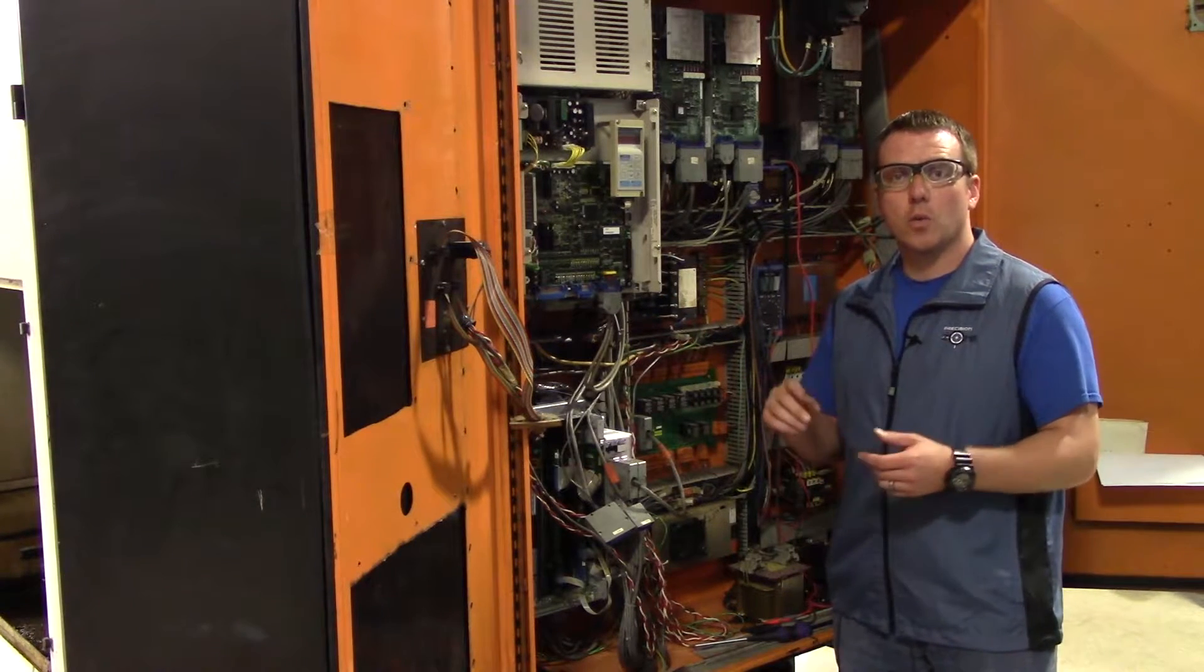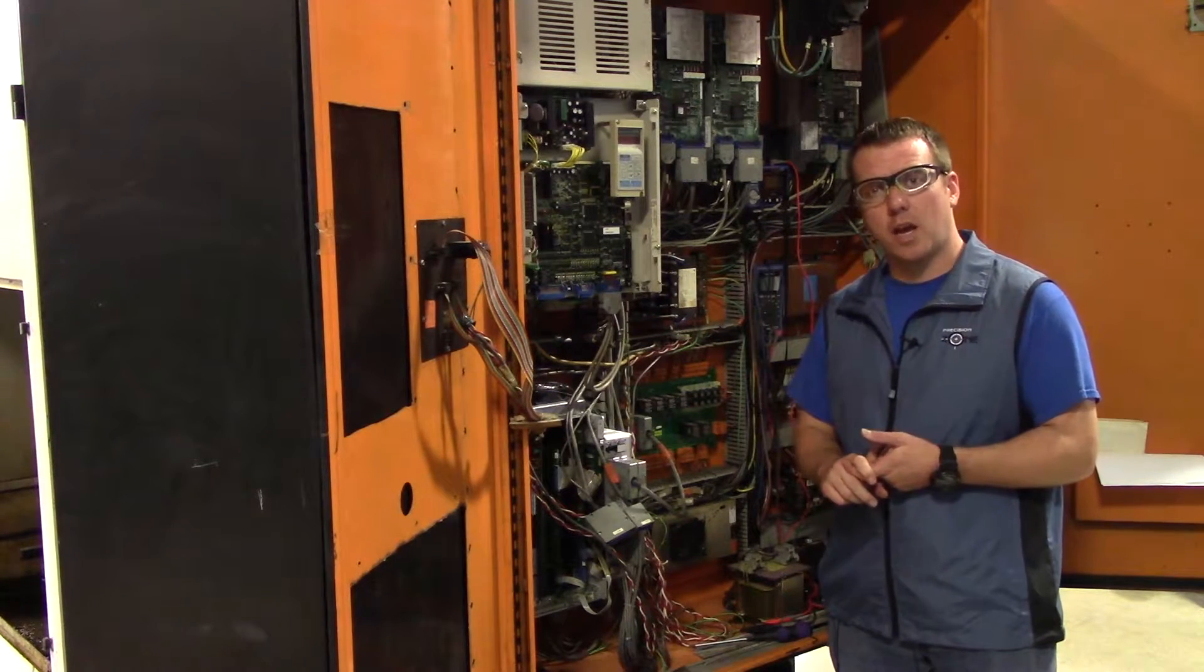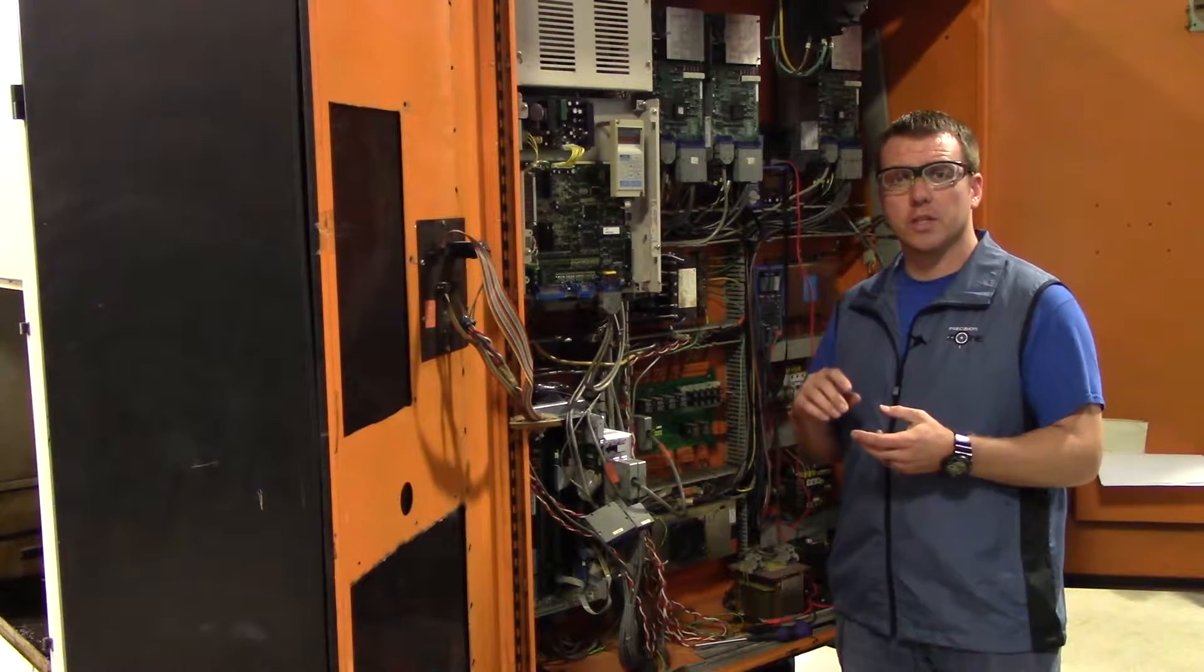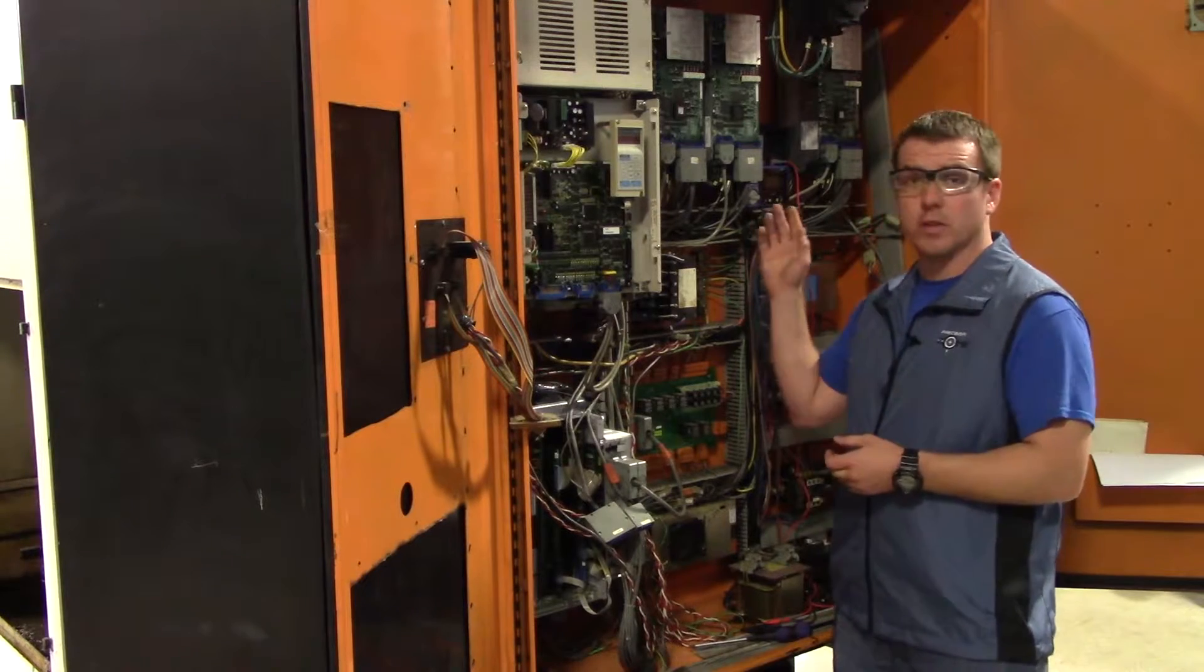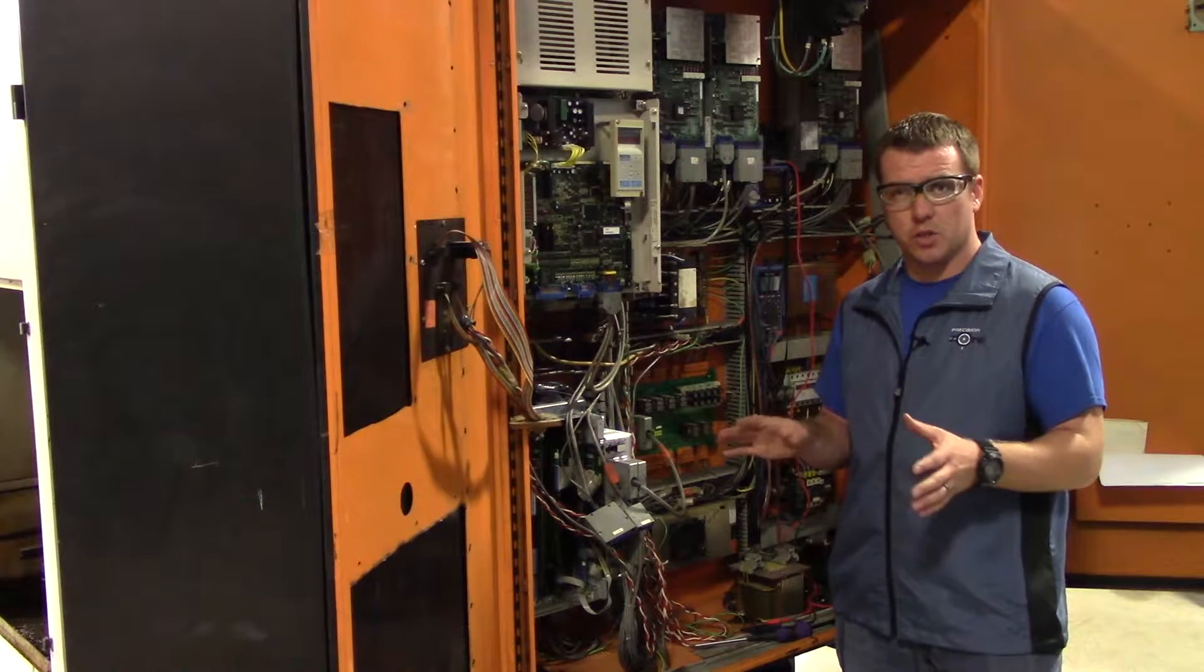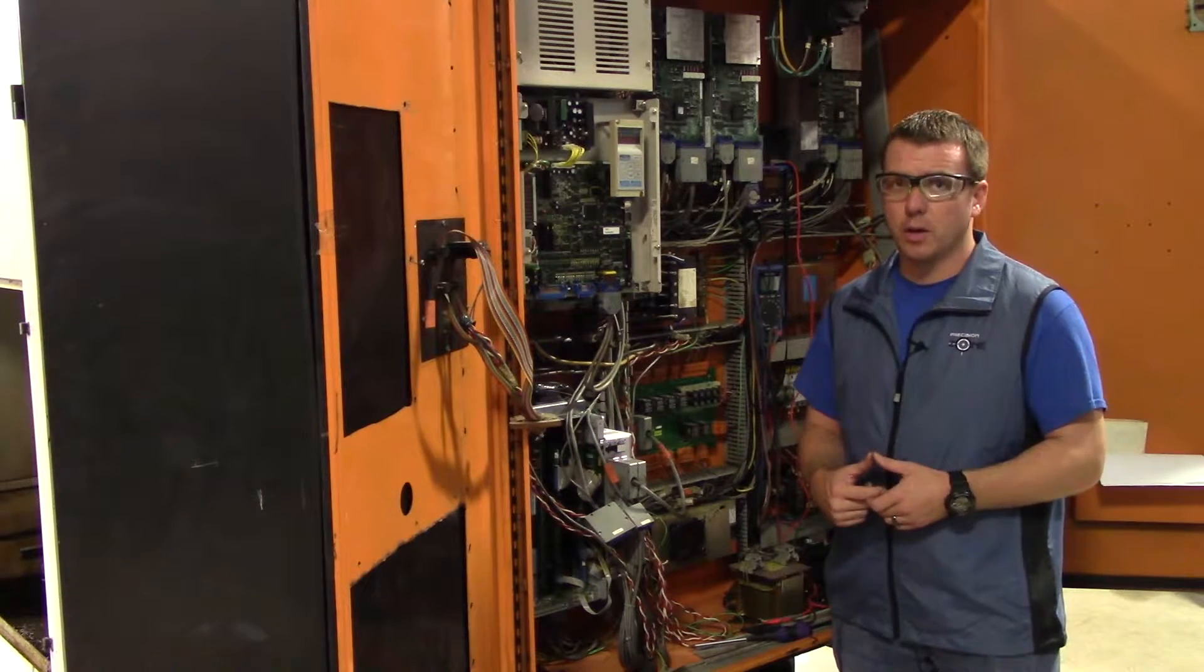So first, I have this machine locked out, tagged out so that it can't get any power to me. I want to emphasize the DC bus on all the drives. You want to make sure that you give the DC bus time to discharge but we're going to double check that.